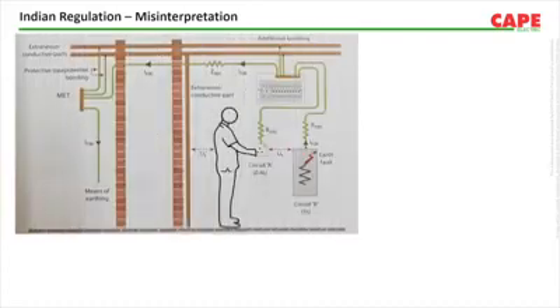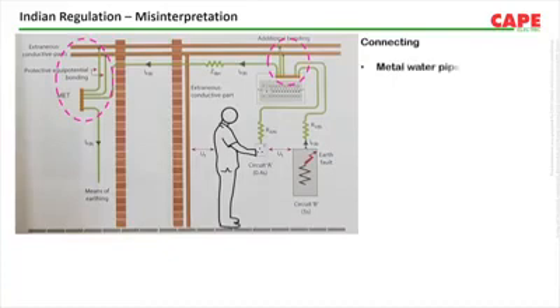Misinterpretation of standards and regulations is the biggest problem in India. For example, in this picture you can find the MET, the main earth terminal, which is an earth bus bar inside the main incoming panel board. Extraneous conductive parts are metal installations such as metal water pipe, gas pipe, facade and so on in a building. In an installation, extraneous conductive parts such as water pipe, gas pipe, metal ducting, and metal frame of wall cladding are connected to the earth bus bar.